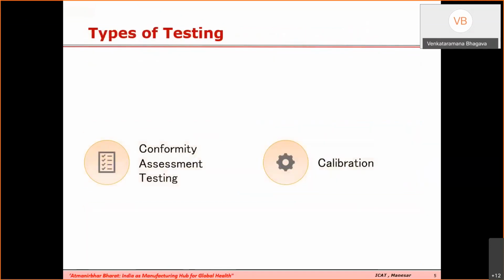Then in medical device testing and validation, there are essentially two types. The first ones are the conformity assessment testing, which is what we are talking about. The second category is the calibration of the devices. So let's say one has a ventilator. Then one needs a gas flow analyzer as well as a variable resistance test lung to calibrate it. Because let us say your lung or my lung, the key mechanical difference is that they will have different mechanical compliances as well as mechanical resistances. So that is a key difference. So these resistance and compliance values will change for different conditions such as ARDS or COPD, or if the lung is of an infant or a female or male, or a sports person, and so on.